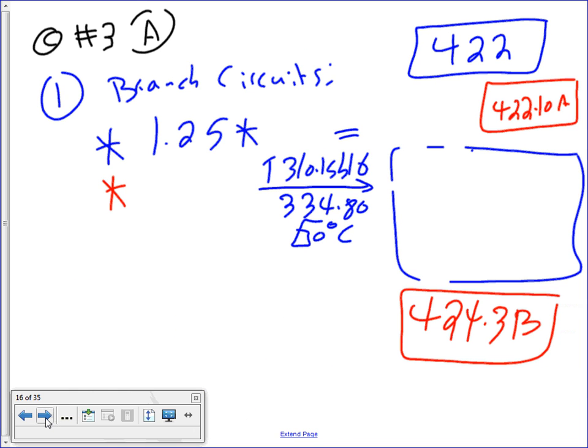Okay, next one. All right, so I have an appliance. Appliances, guys, is 422 as well. And since they're also heaters, 424 also applies to them. So let's go ahead and find the branch circuit before we do any calculation. I have a 95 amp. Multiplied by 1.25. This is from 422.10(A), same thing for appliances. That gives you 118.8 amps.